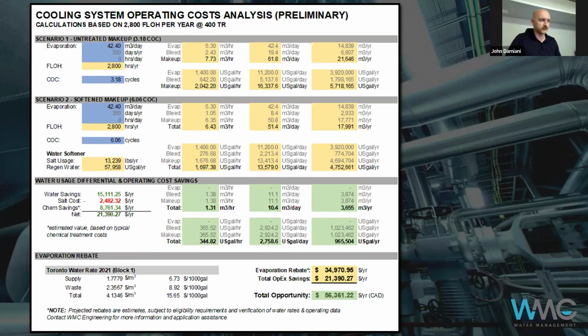The green numbers toward the bottom show water savings. There is a cost involved in operating a softener—you have to pay for salt—but there are also chemical savings, giving a net savings overall. In this case, we also calculated an evaporation rebate based on known evaporation, adding up to over $50,000 per year in savings. Comparing that to the cost of implementing the water softener, you'll likely see a very fast payback on something like this.